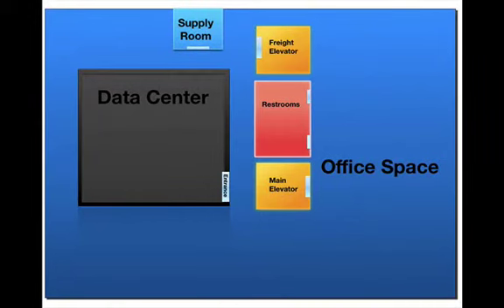This is the floor plan of the entire floor. For 20 racks, a data center will fit well under 1,000 square feet. Since the data center is located within the office space of a multi-story building, it will have some restrictions as to its location. While the office building has windows, the data center should ideally have no windows and only a single point of entry. Therefore, the data center will be sealed off as a separate room with walls that extend from floor to ceiling and have no other accessibility except for the main entrance.